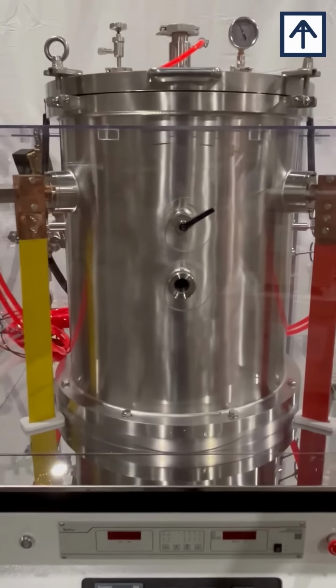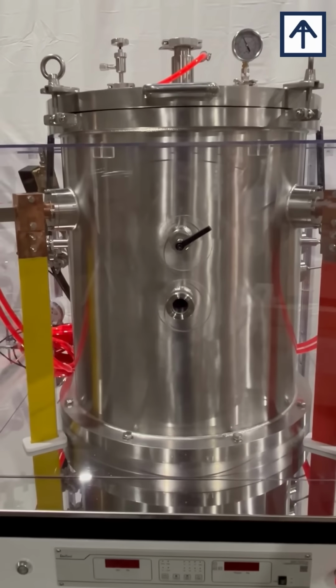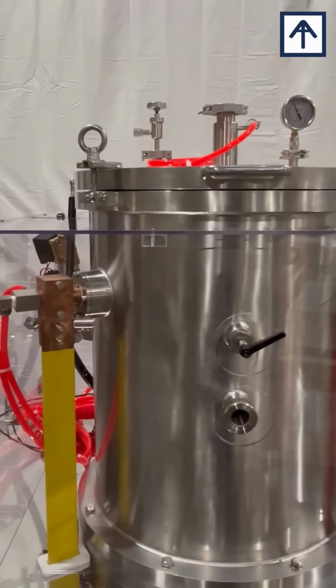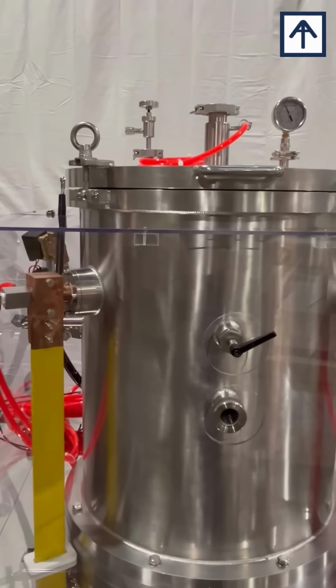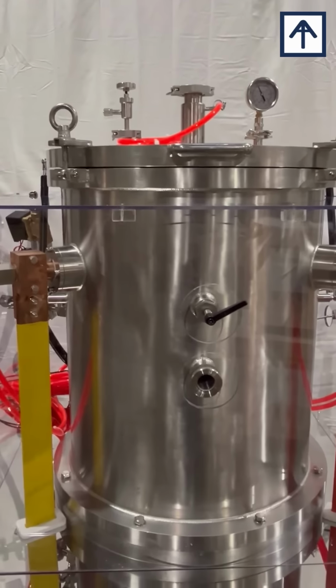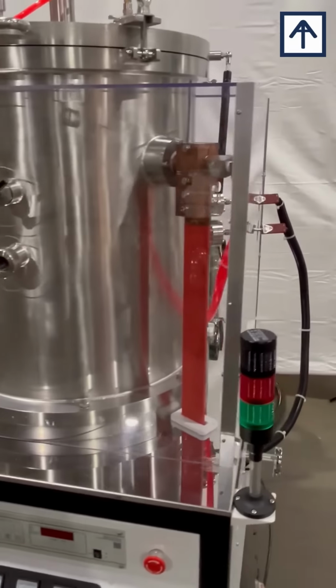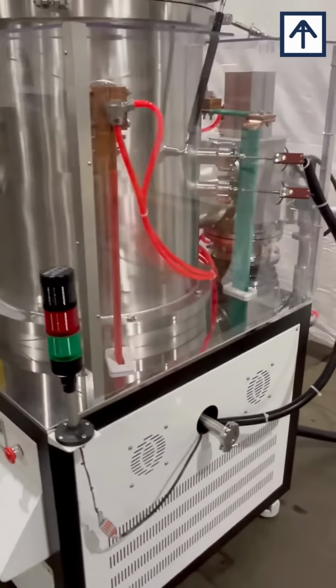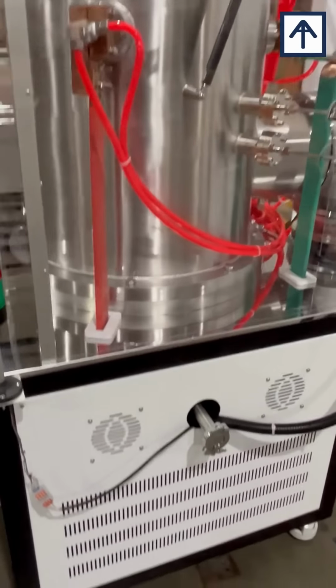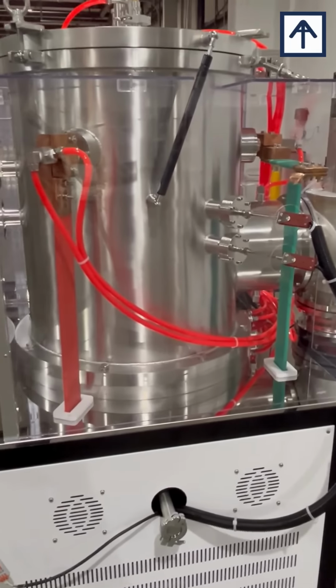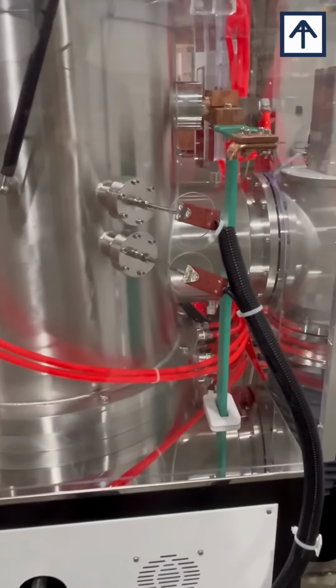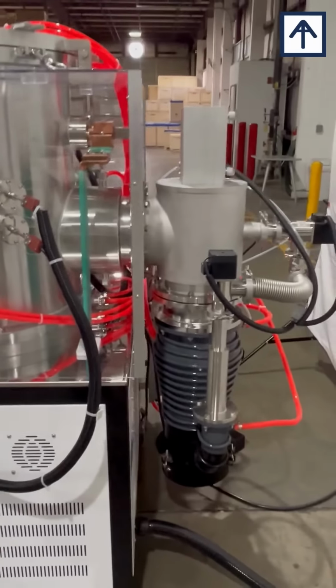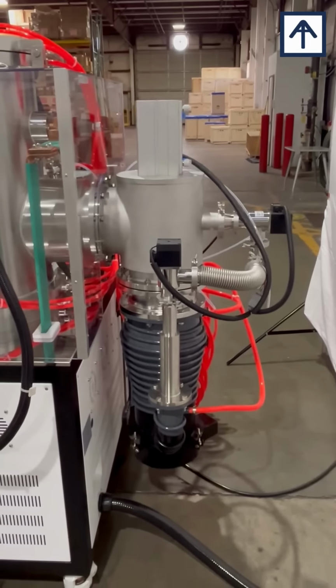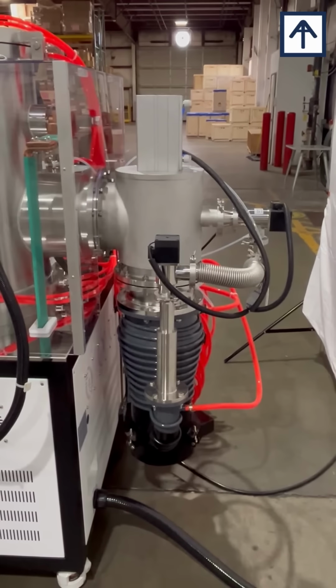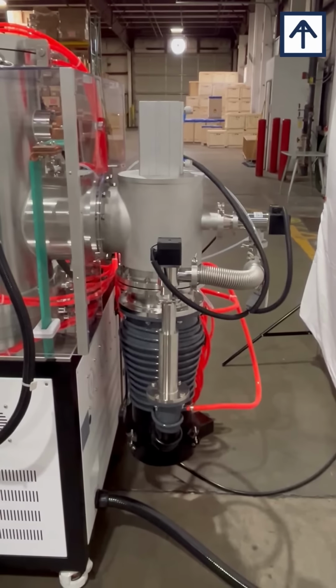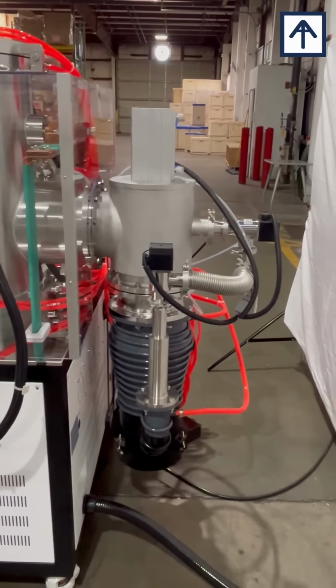As you can see, it has the side glass, the lid with the pressure gauge on top, and then your pressure release or the vacuum release on the top, or for your inert gas outlet as well. And then if I walk you towards the right of the unit, you can see the alarm sensor, the inert gas inlet on the bottom, as well as your primary and your secondary thermocouples right there. And then if you go to the back of the system, the unit can be either configured with a turbo pump or a diffusion pump, as I mentioned. And then this current system is equipped with the diffusion pump.